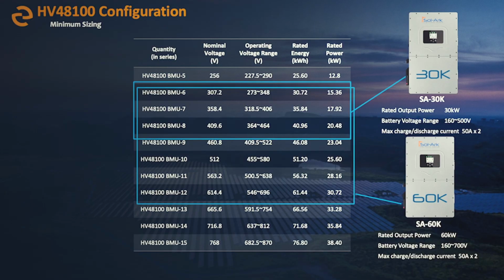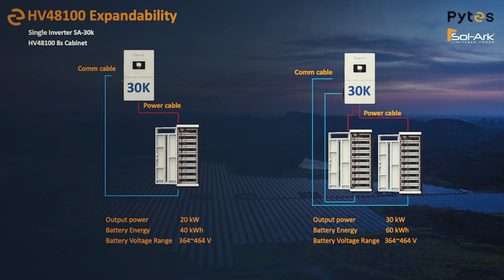Both of these inverters, I'll add as well, have 2 battery inputs. So the installation or the configuration, when you stick to a 1-to-1 or a 2-to-1 ratio, is super, super easy. The packing list for the high voltage batteries comes with everything you need to connect not just the batteries together in the cabinet, but to connect that cabinet to the inverter. You can see here with the 30K, we've got 2 stacks, so 60 kilowatt hours total. Each one of these is feeding into a separate independent input on the inverter. So these actually aren't in parallel. The inverter treats these as separate batteries.